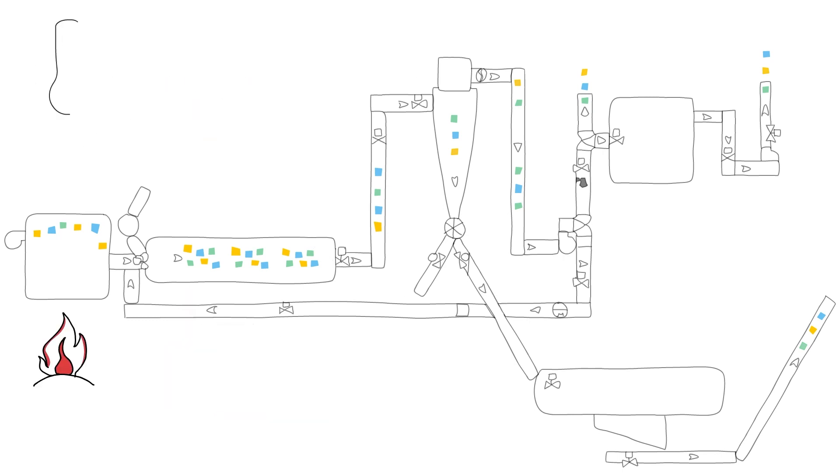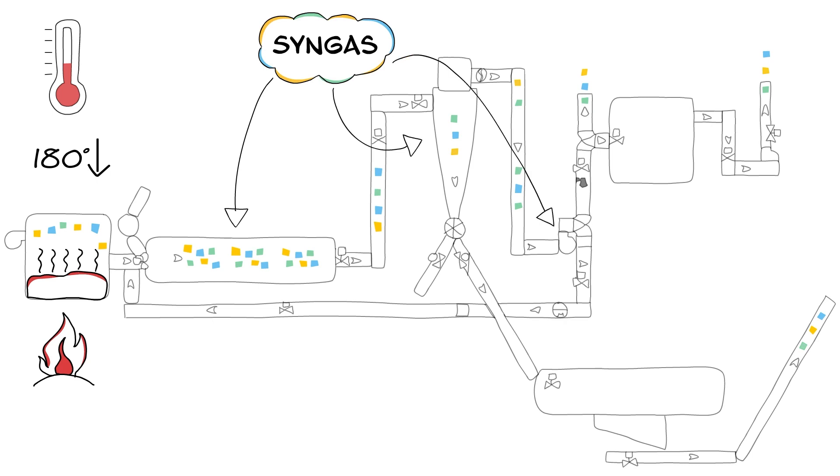Processes that burn wood at high temperatures or that gasify and burn wood will usually burn off syngas. However, mid to low combustion temperatures between 140 and 180 degrees Celsius, depending on the wood species, can cause incomplete combustion, which may lead to syngas generation within the drying system.